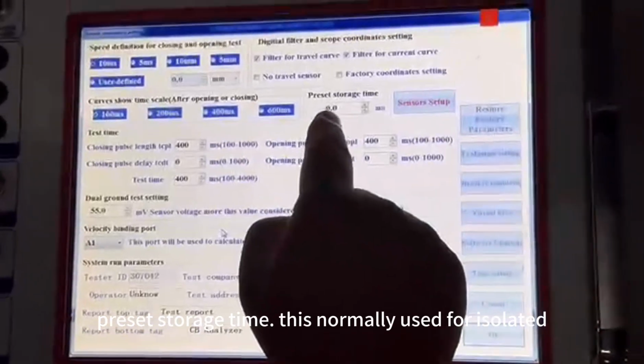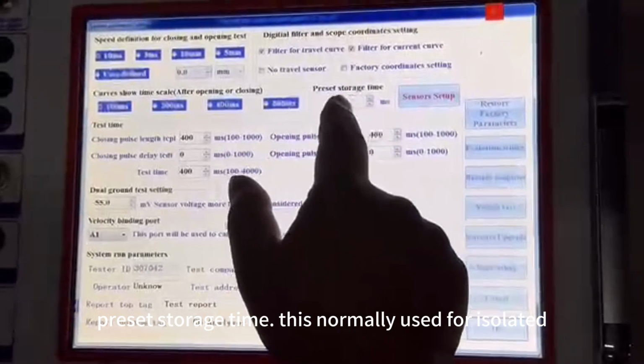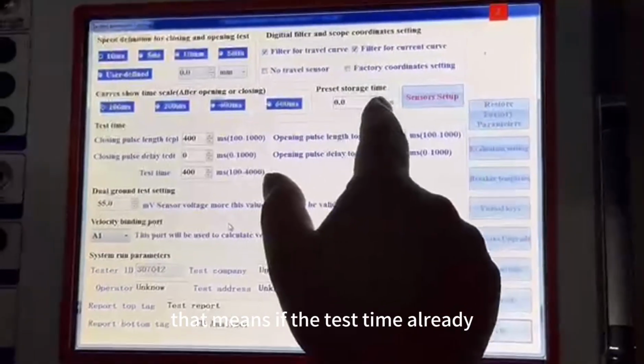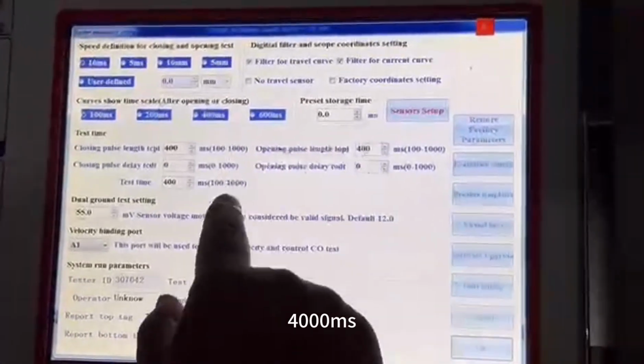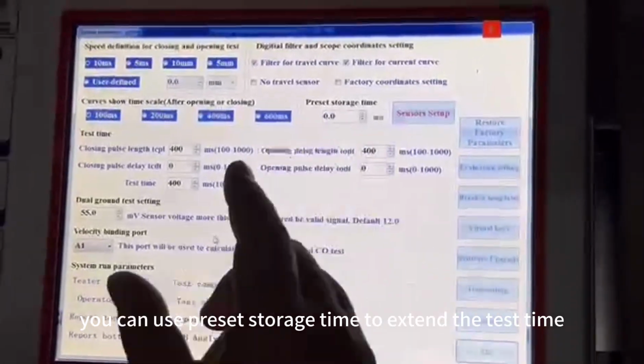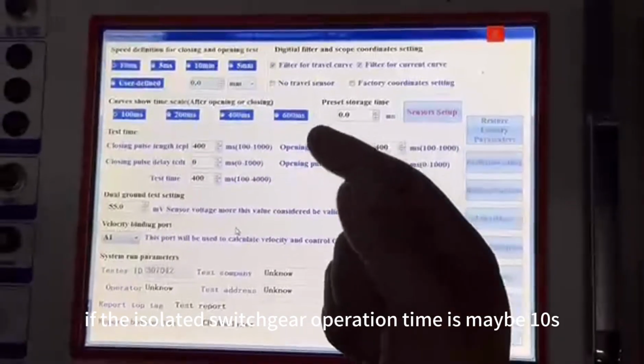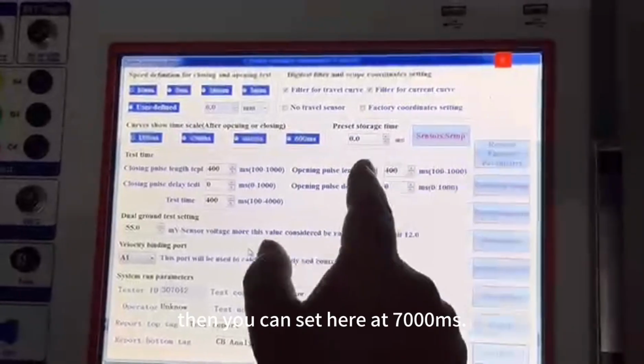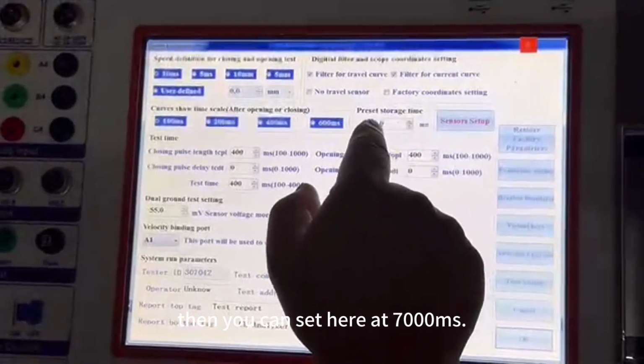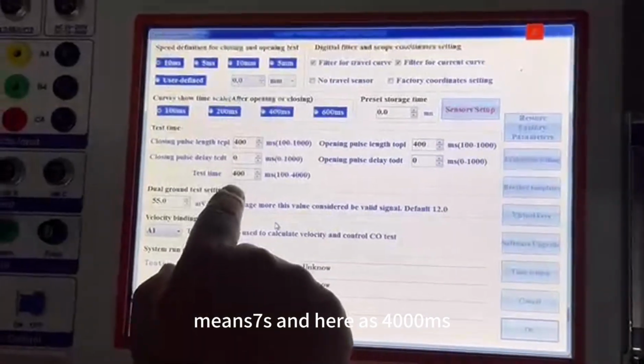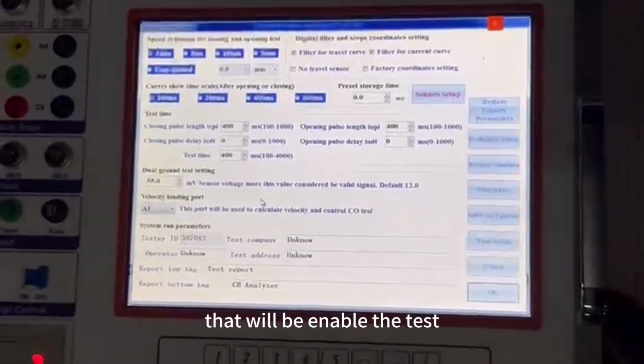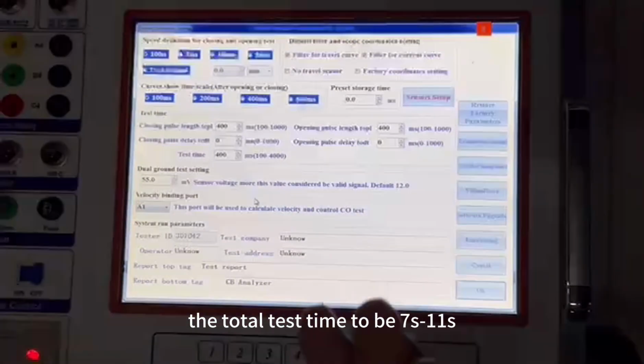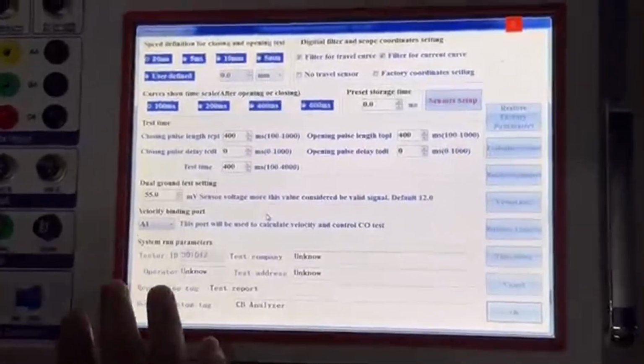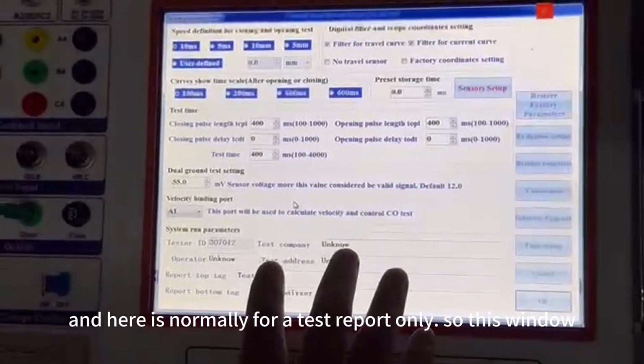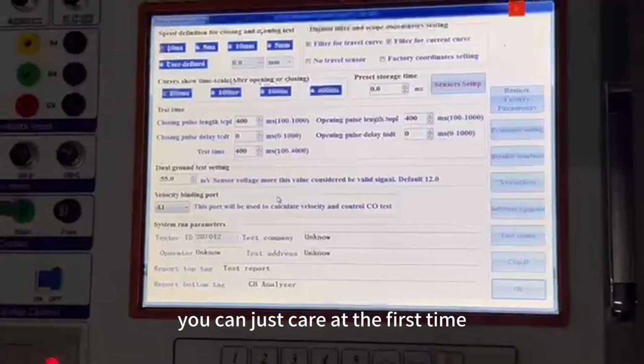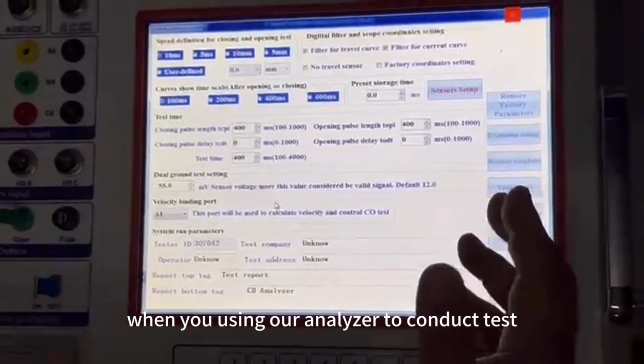And here, preset storage time. This is normally used for isolated switch gear. That means if the test time already exceeds the maximum 4,000 milliseconds, you can use preset storage time to extend the test time. For example, if the isolated switch gear operation time is maybe 10 seconds, then you can set in here 7,000 milliseconds, meaning 7 seconds, and here 4,000 milliseconds. That will enable the total test time to be 7 seconds to 11 seconds. And here is normally for test report editing. So this window, you can just set at the first time when you use our analyzer to conduct a test.